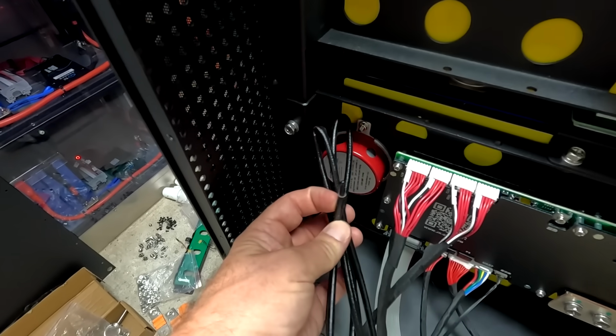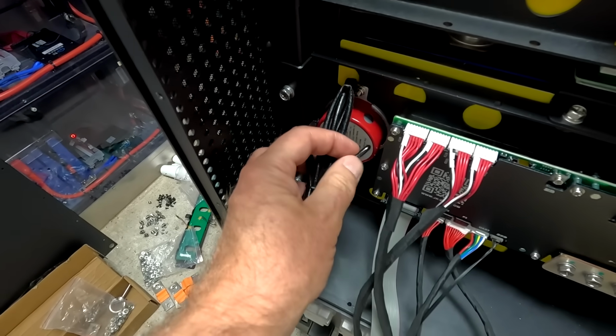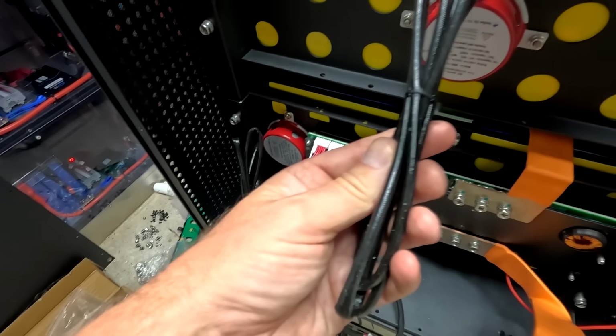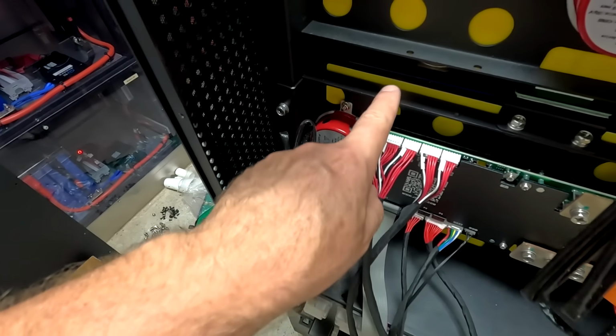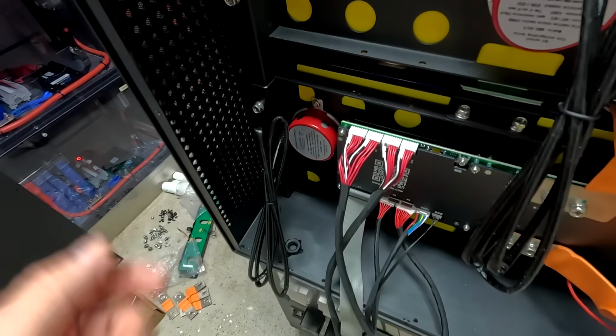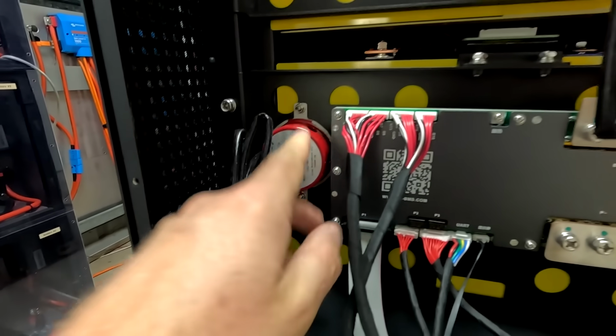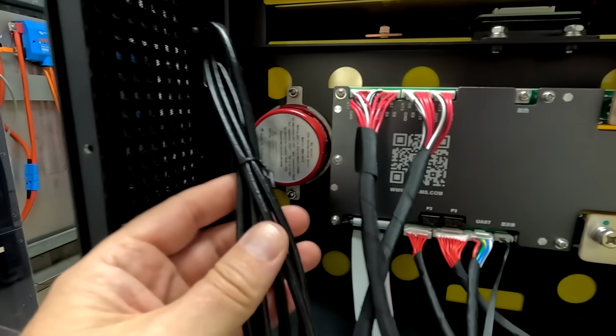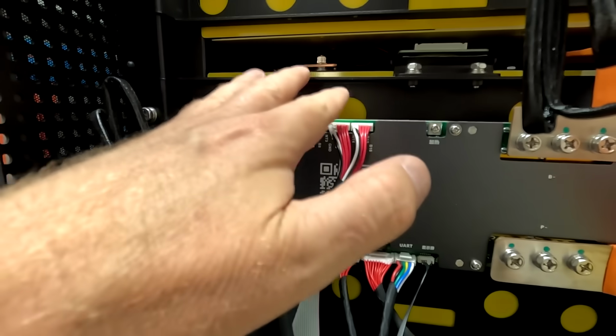And I'm also not sure where to mount these trigger sensors here for the fire extinguishers. I've got 2 of them, should be one in between the batteries somewhere. But they are clearly not made for preventing a battery fire - they will probably put out a cable fire, but not if the batteries are burning. Which they actually can't, because this is lithium iron phosphate - they don't burn, at least not very easily.